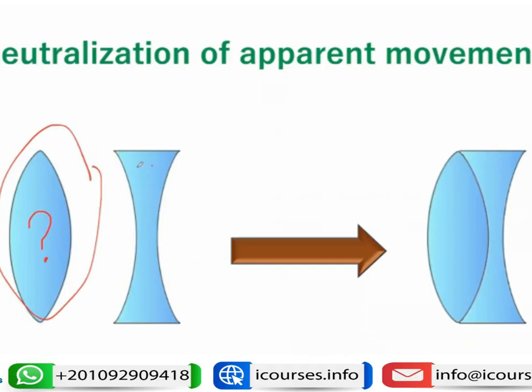So you will know that it is a plus lens. Then you will combine it with a minus lens like this, and then you rotate or remove this combination again over the cross. If there is no movement, then this minus lens has the same power as the plus lens, but with a different sign. So it is now acting as a parallel plate of glass with no refraction.